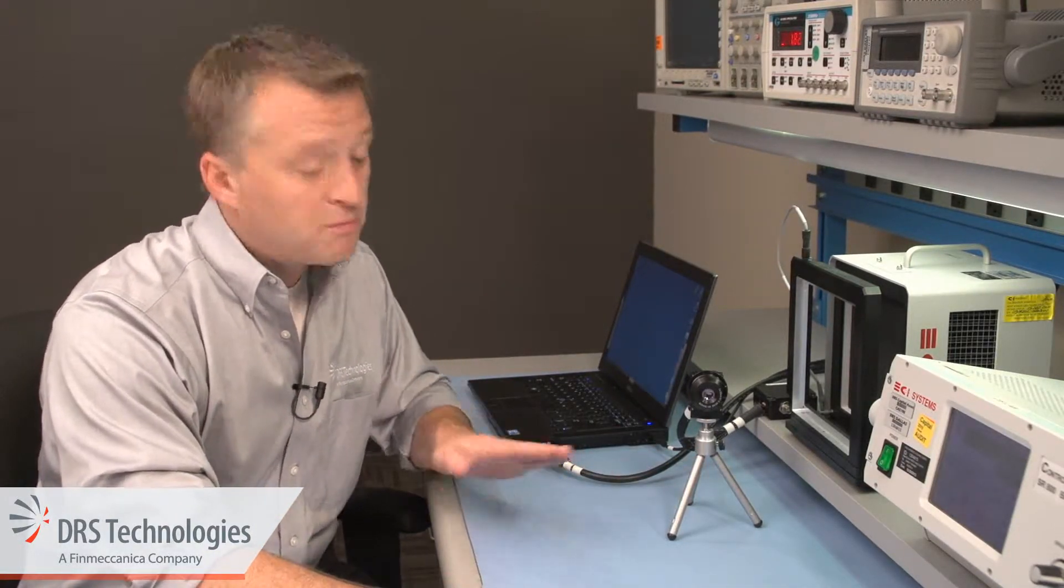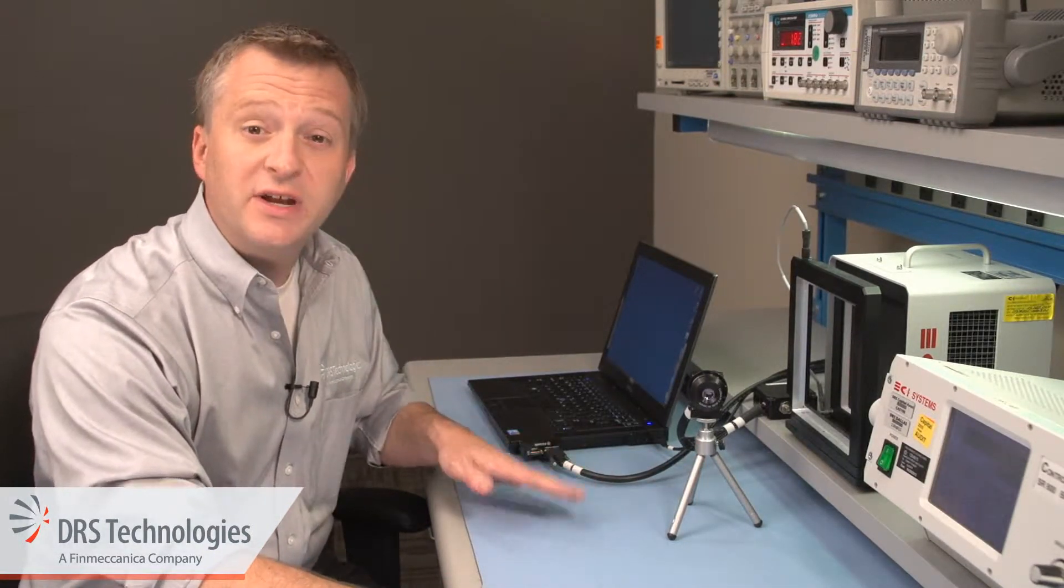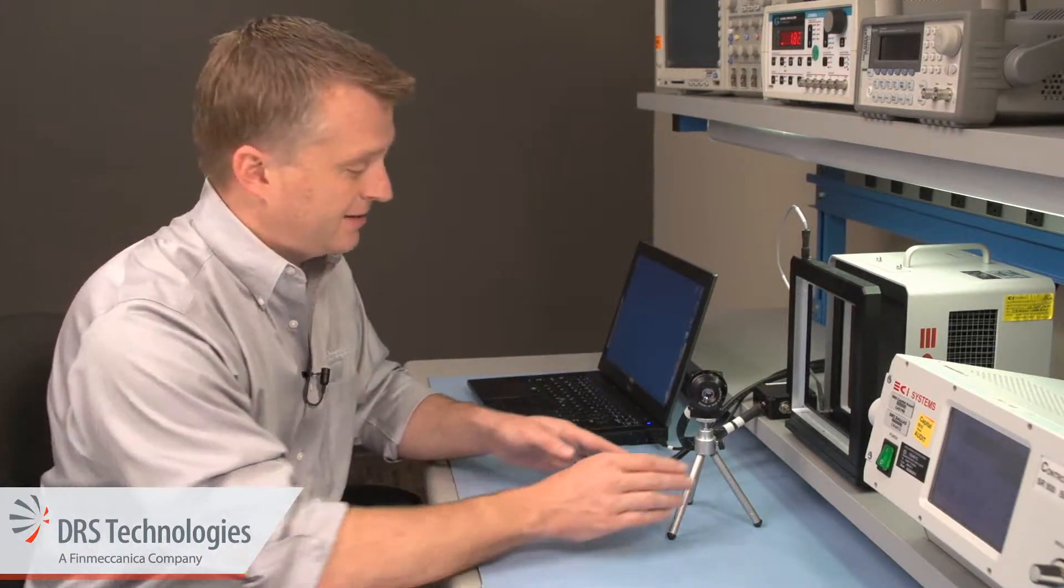Okay, the camera's been at a stable operational temperature for 30 minutes, and the blackbody's reached 12 degrees Celsius. Now, point the camera so that it's staring into the uniform temperature target in the blackbody.